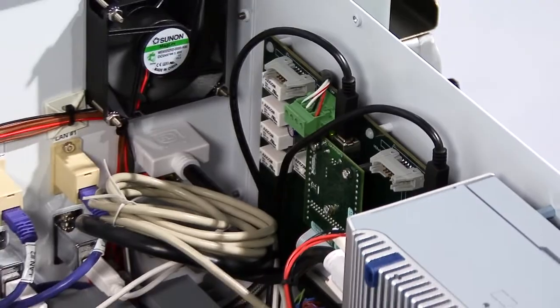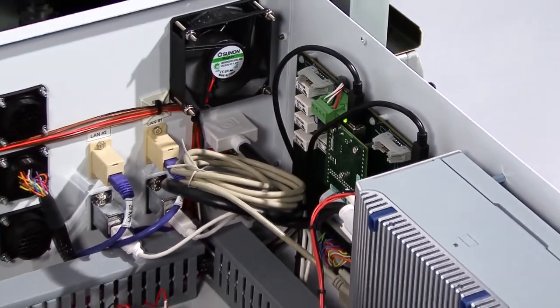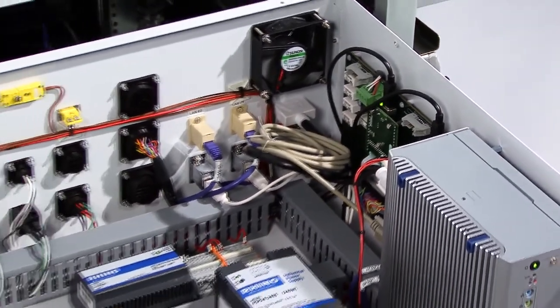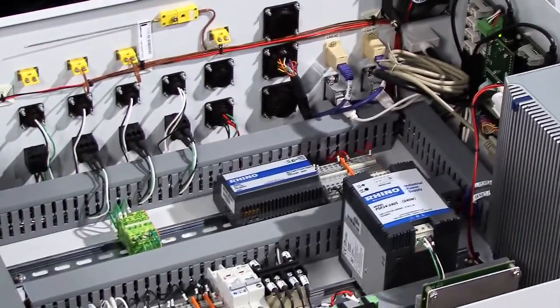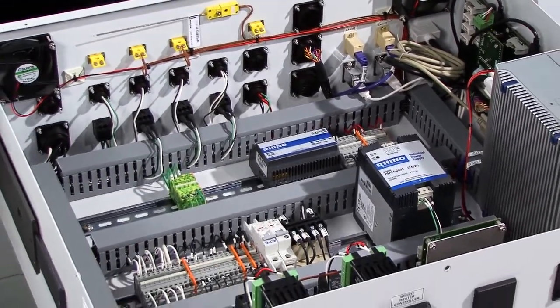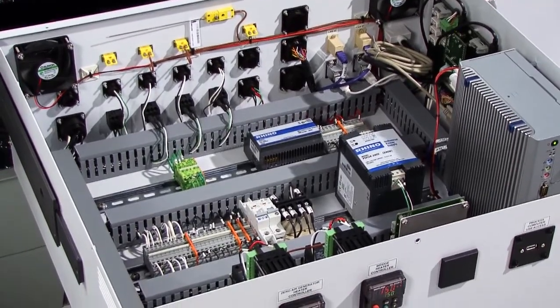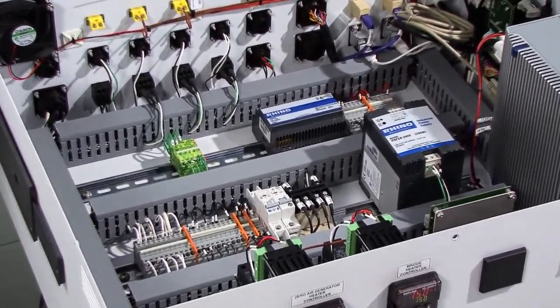The system communicates with the plant control system in an analog or digital format. Digital formats include Modbus and OPC and are the most popular choices given the incredible volume of analytical information that one of our systems yields relative to a classical process GC.